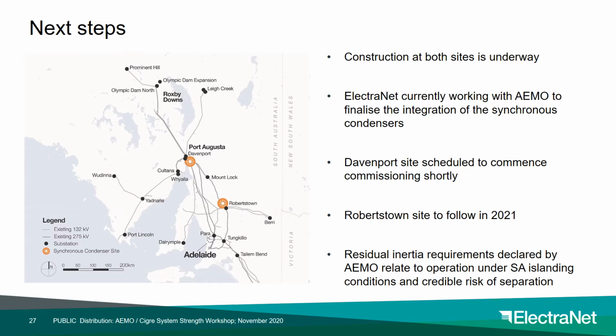The installation of synchronous condensers resolves the system strength and synchronous inertia gaps declared by AEMO. However, the SA grid requires more than strength and synchronous inertia in order to operate securely, particularly when at risk of islanding from the NEM. To enable sufficient frequency control, generation ramping capability and supply and demand balancing is necessary, and sufficient levels must be provided both for intact and islanded conditions. AEMO has declared residual inertial requirements related to fast frequency response capability, and Electranet is working with AEMO to resolve these new requirements.